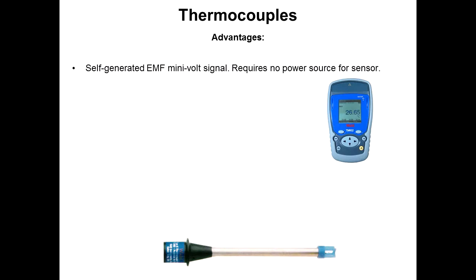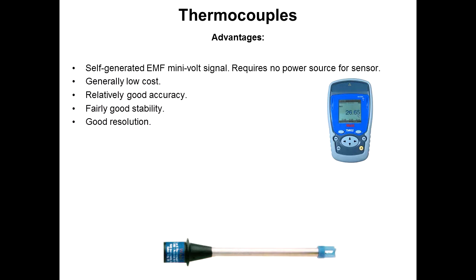So advantages: it's a self-generating signal off of a thermocouple. It needs no external power source to power the probe. They're low cost, relatively good accuracy, fairly good stability, good resolution, generally very fast. Speed of response is always a function of the probe mass. Thermocouples have the least mass of any of the sensors, so they're the fastest.